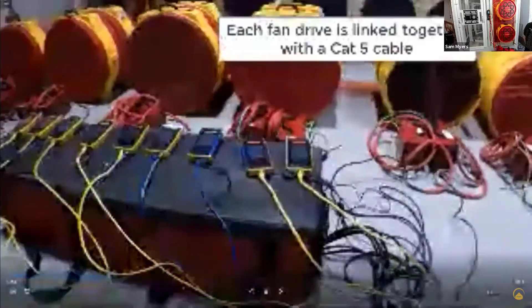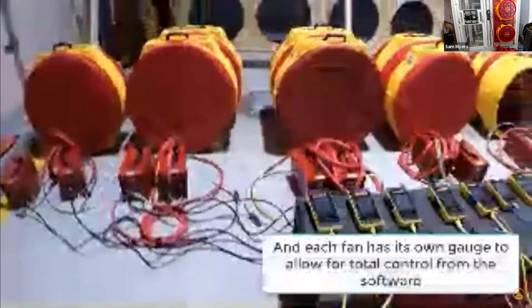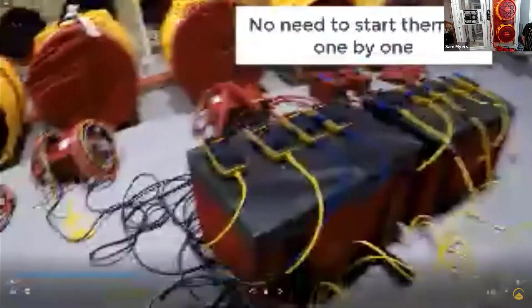As each gauge is connected to the switch box, each one of these drives is connected to the next one. That's the daisy chain configuration I discussed earlier, so each of these fans runs at the same rate at the same time. Another Cat 5 cable goes into one of these variable speed drives, and another one goes out to the next one, so you don't have to start each fan one by one. You can crank them all up at once.